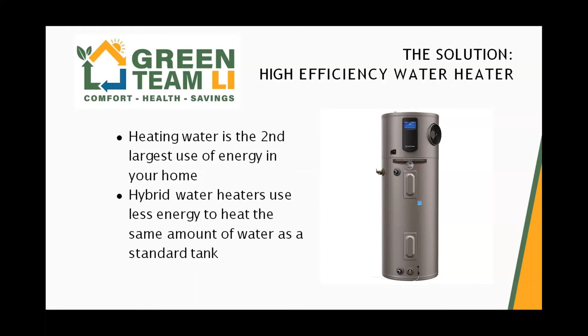So it's taking 1 unit of electricity and gathering 2.5 to 3 times as much additional heat from its environment and putting that in the water. And so now we can have much higher efficiencies than we ever imagined through this kind of magic of the heat pump. That's one of the great updates that we've seen in the last 5 years of these heat pump hot water heaters. Really an amazing piece of technology, and they've become quite mainstream. We're doing literally hundreds of these now a year, and I think this is going to become the standard for most people pretty soon.